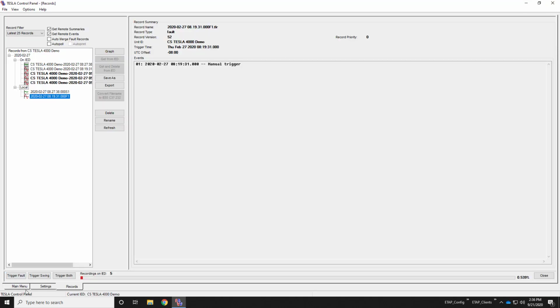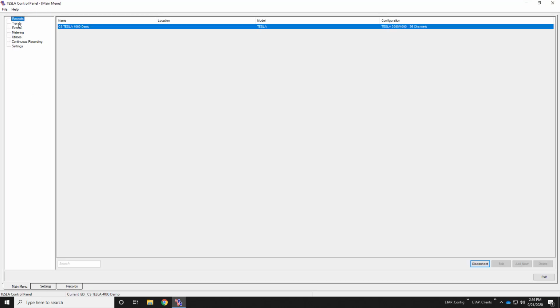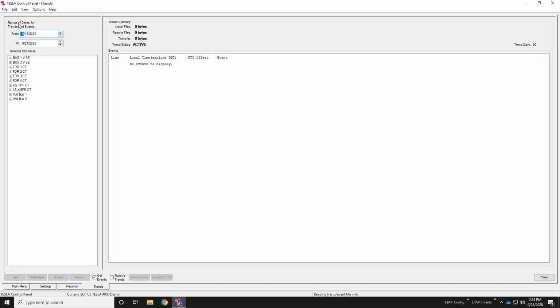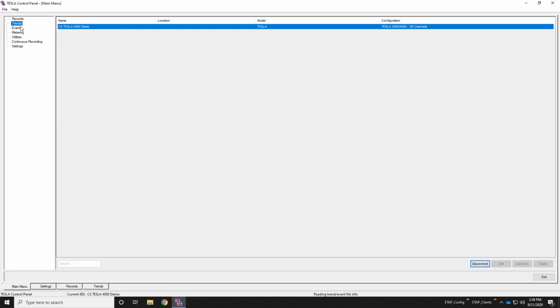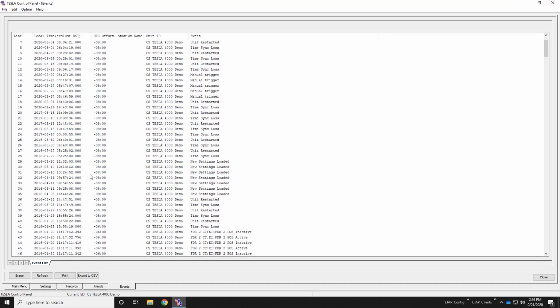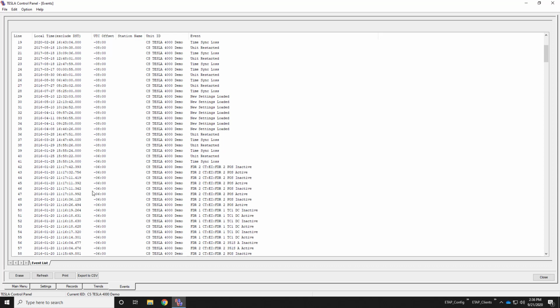Next, I will move to the trends. Here we can actually do real-time trends of data and events. These are sequence of events. For instance, when a circuit breaker trips or a value goes past its thresholds, we'll generate an event here. These events can be passed to the master via DNP as an SOE, IEC 61850, etc. So all of these events are available internally in the device, as well as available to the SCADA system.